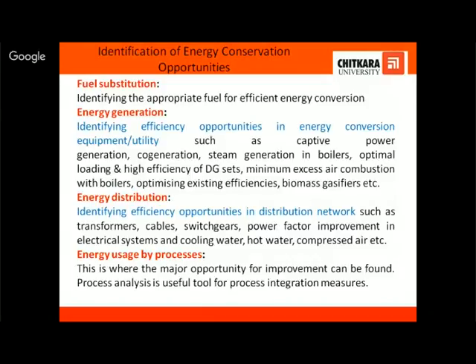Then when we talk about the generation process, find out if we can identify any energy efficient opportunities in the energy conversion equipment, such as captive power generation, cogeneration, steam generation in boilers. DG sets are normally used in all the industries, either for the peak load or whenever there is a breakdown of the grid. So what is the optimal loading and high efficiency of the DG sets? Then if boilers are being used, what is the minimum excess air combustion? What about optimizing existing efficiencies?